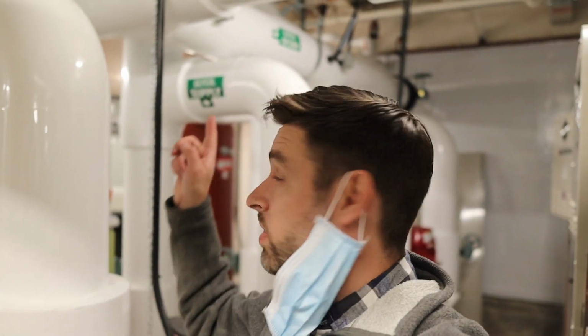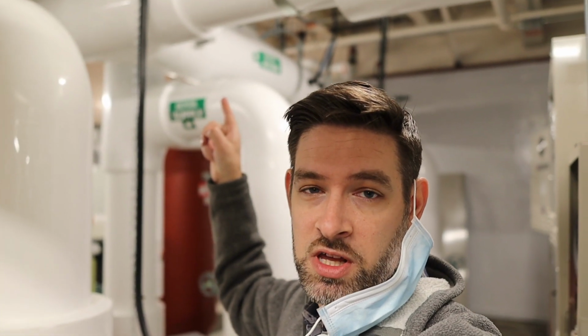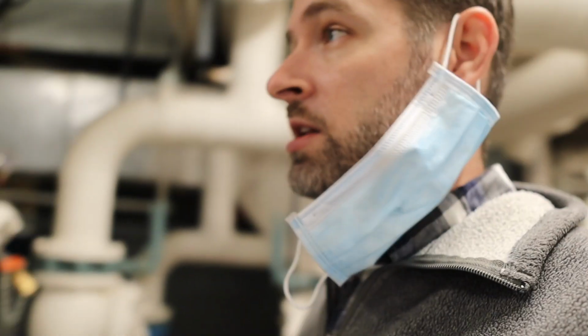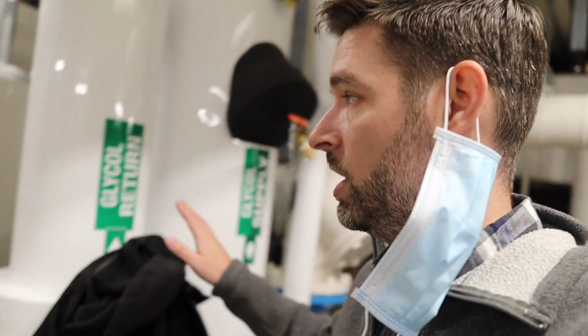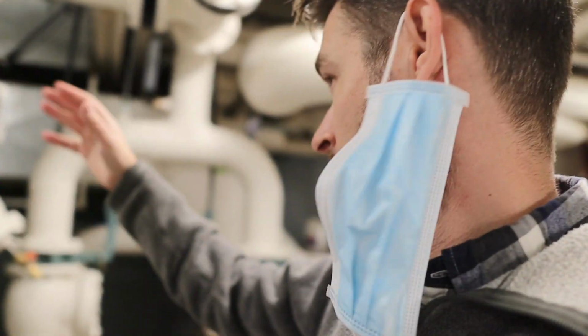There's a good view. That main pipe right there is what feeds back out to the geothermal loop field, and on the other side is the supply from the loop field. So those pipes come in to this low temperature chiller plant right here, and the job of the chiller plant is really to extract the energy from the geothermal loop and boost it. Actually not that far. On design, it's only boosting it up to about 70 degrees Fahrenheit on the other side of the chiller.